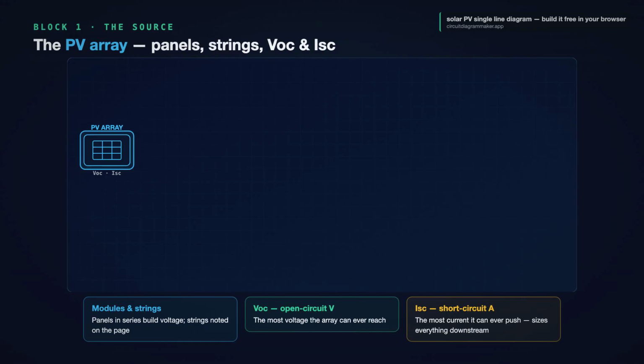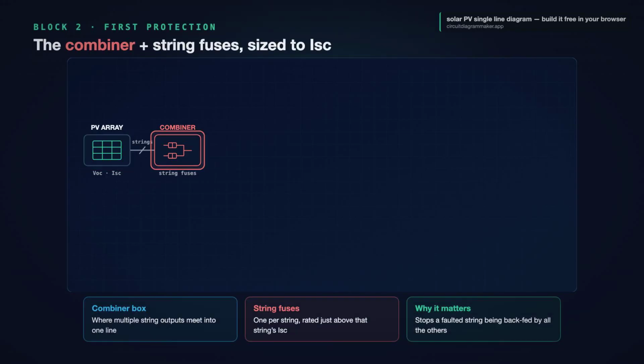Block 2, the string combiner and the DC overcurrent protection. When you have more than one string, their outputs meet at a combiner box. And right there, each string gets a string fuse, sized just above that string's ISC, so a fault in one string cannot be backfed by all the others. This is the first real protection device on the drawing, and it is the one inspectors look for first.